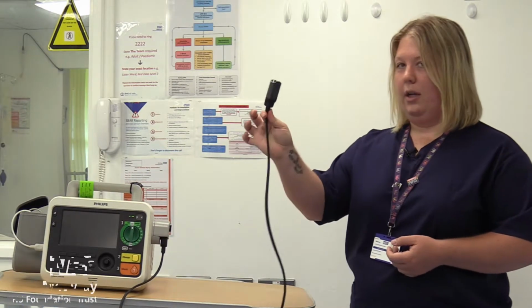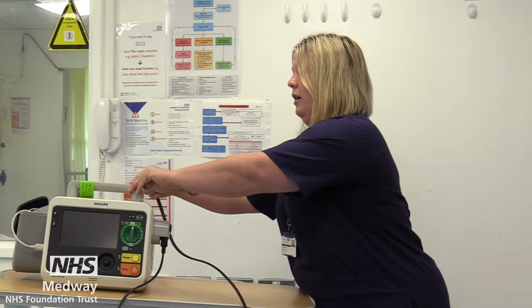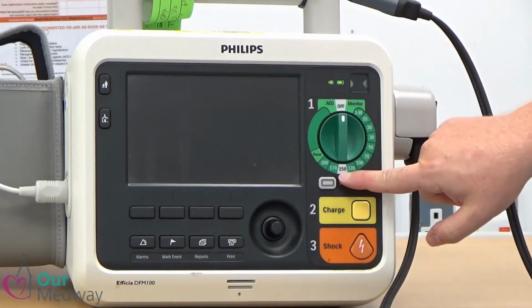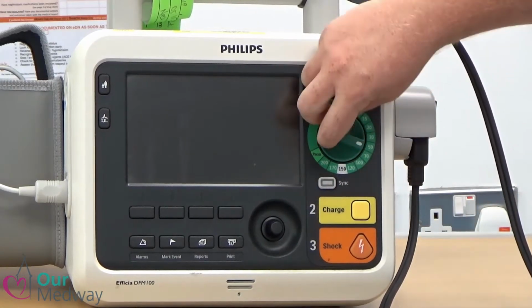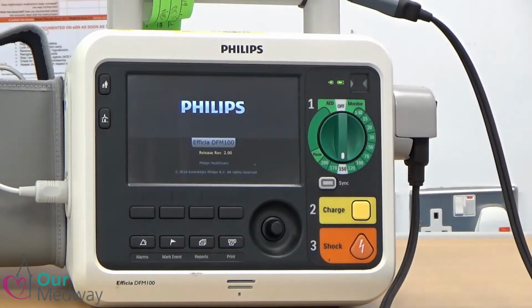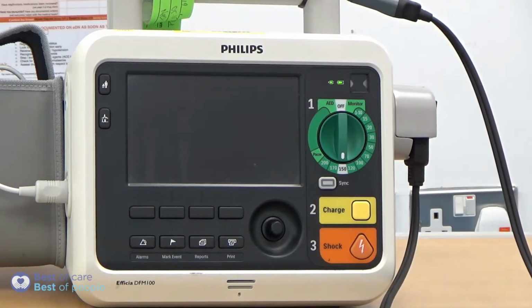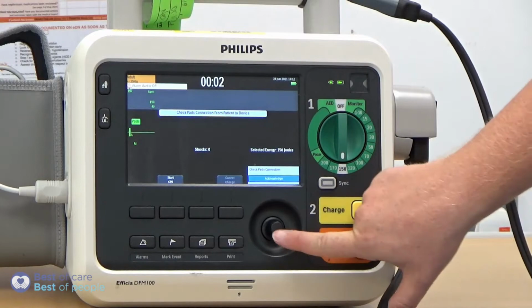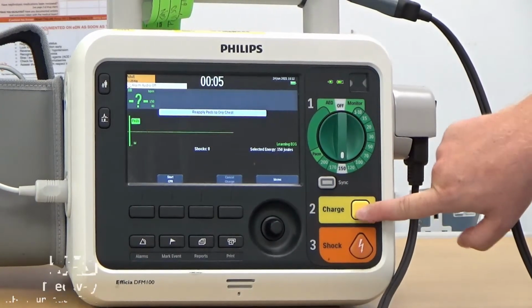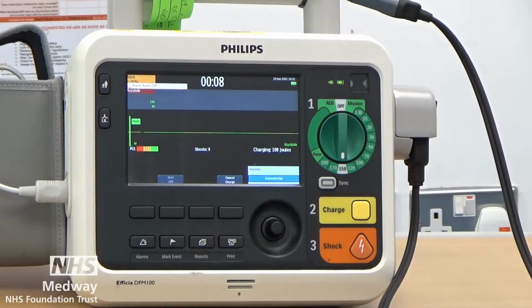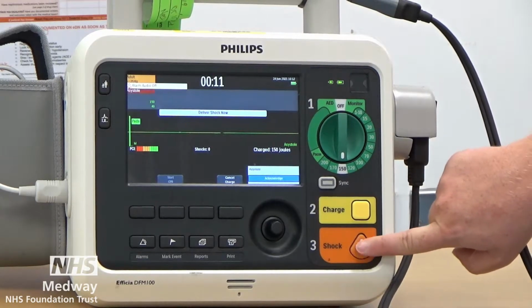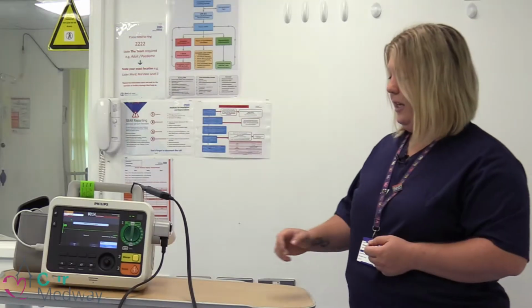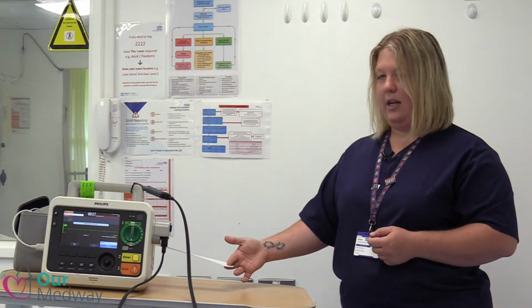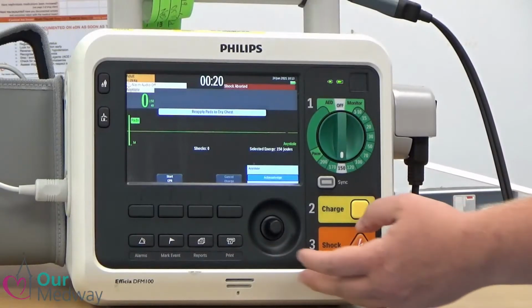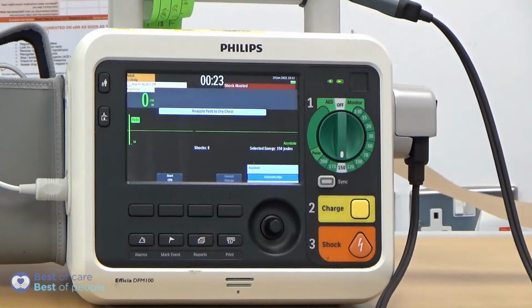So I'm going to start by putting my pads cable onto my test plug, and the daily check is really quick and simple to do. I'm going to go straight round to 150 on the dial. This will alarm at us because obviously it's on a test plug and not a real patient, but we can silence the alarm just by acknowledging it there. We're going to charge and we will shock once this flashes. Shock cancelled. And you'll notice that the defibrillator is now printing off that test strip. Once it gets to the end, if we hit the print button, that will stop.